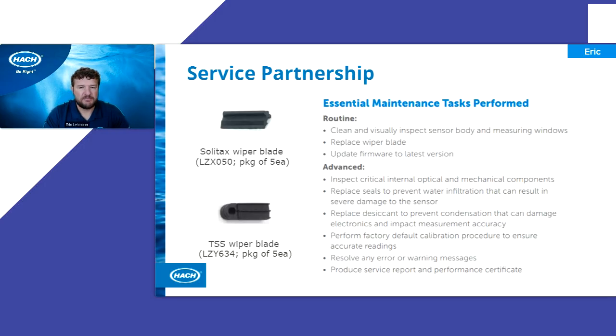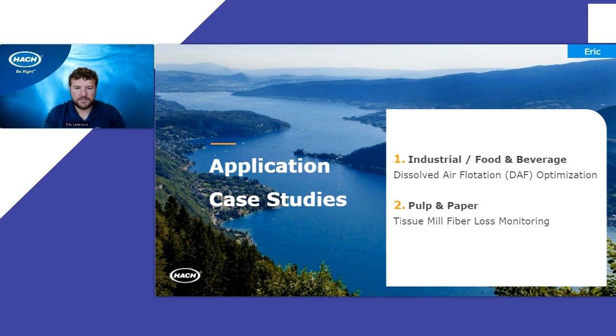Some basic maintenance for the probes. Of course, it does have a wiper, similar to the windshield wiper on your vehicle. That does need to be replaced every so often, about every 20,000 wipes or 20,000 cycles. So fairly easy to maintain. Some of the more advanced maintenance: there are some seals inside the probe that need to be replaced about every 2 years or so. There's a desiccant inside to prevent any sort of moisture being built up. So there will be some maintenance involved for these probes, but very minimal. So let's get into some examples of where these are used.